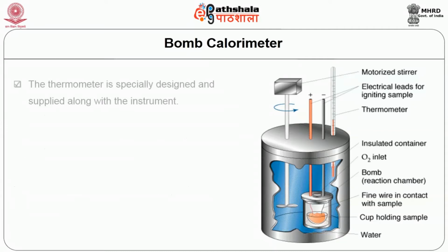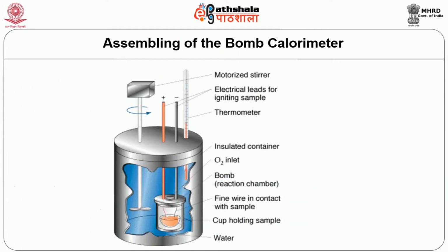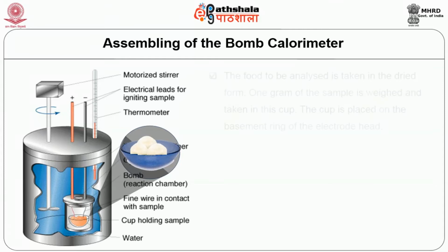The thermometer is specially designed and supplied along with the instrument. The stirrer is attached to the lid of the jacket for maintaining the uniform temperature of water in the bucket. Next aspect is assembling of the bomb.